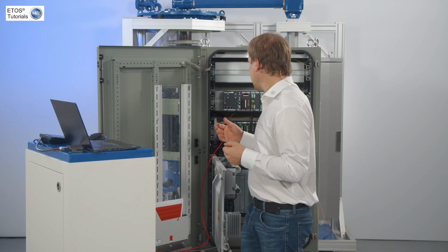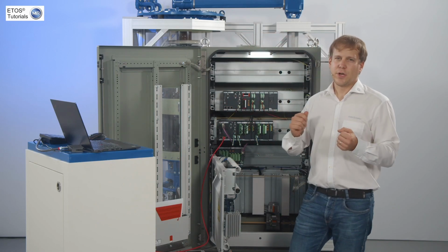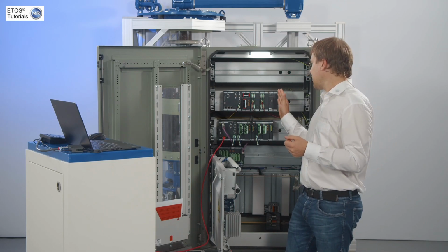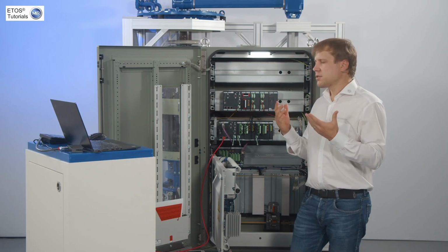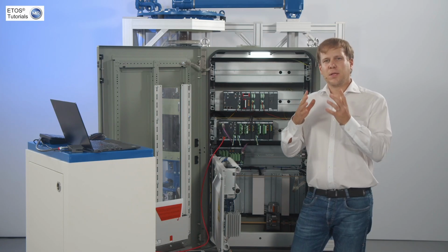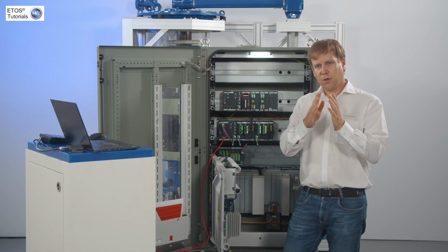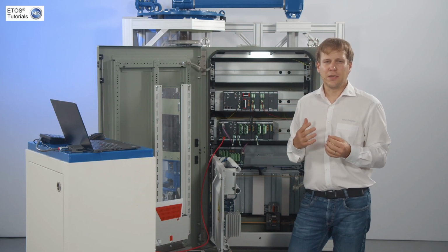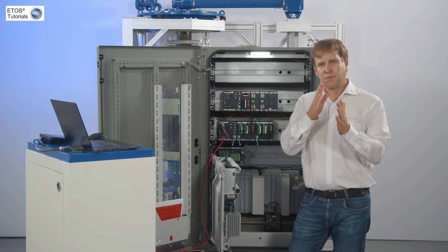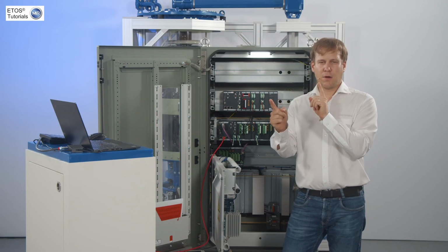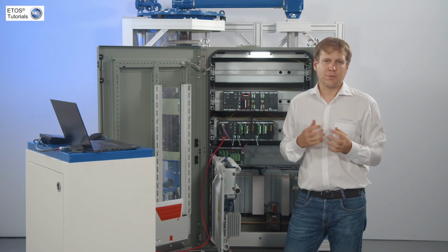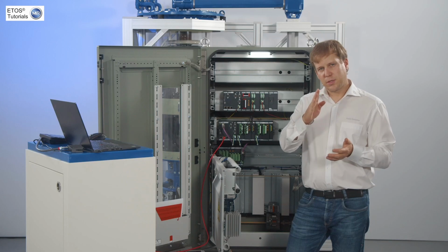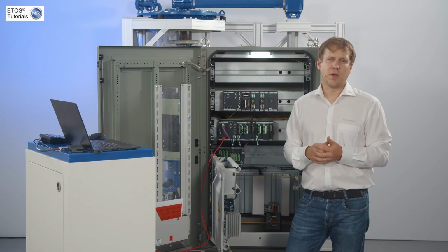Now the next one is related to the configuration of ETOS. In case you expand the system and add another card, or you need to replace a card for any reason, then take extra caution to install the cards card by card, slot by slot, the way it's mentioned in the electrical diagram. Because if you mix up the slots, if you rotate the cards, then the system won't be able to start up properly and will bring up an error message. This is quite common because the system will check card by card if they are available.